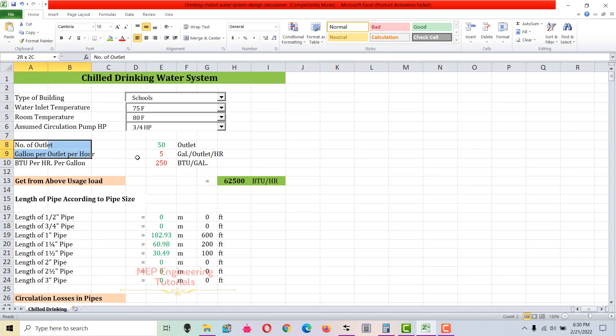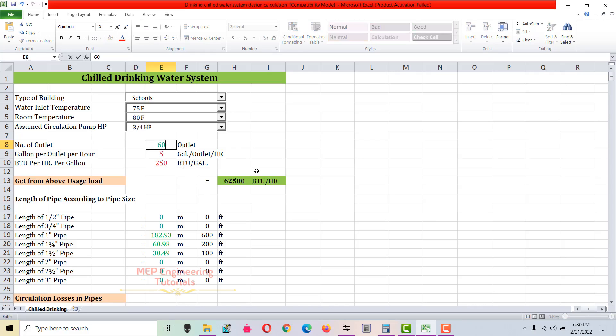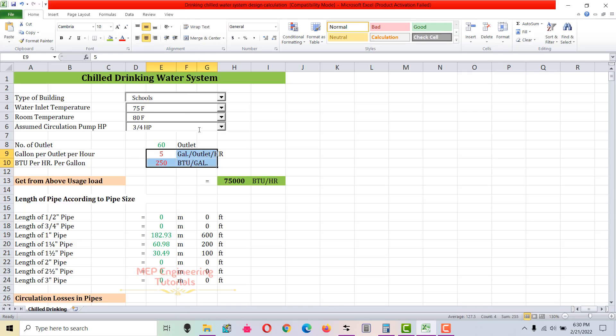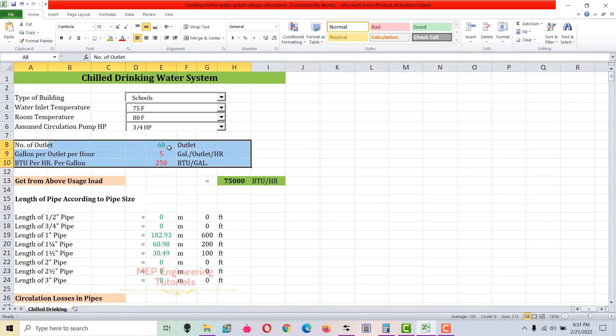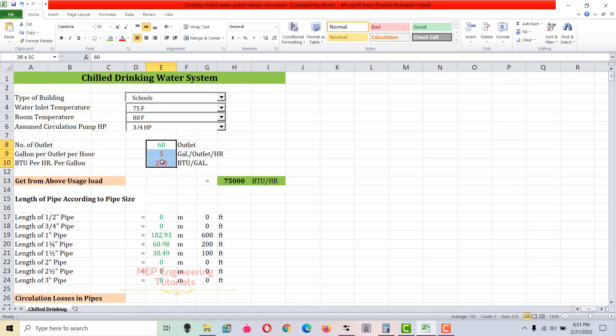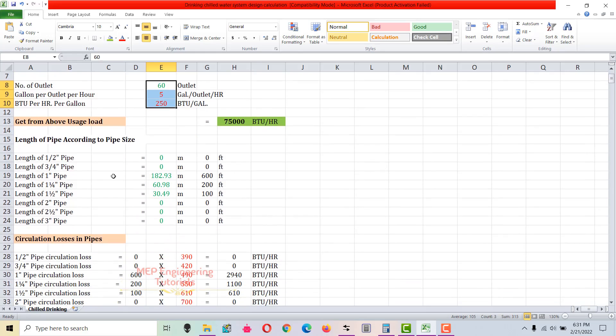Next, you have to count the number of outlets. Green color is the input from the user, so you have to go to the drawing, count the number of outlets, and enter it here. Let's say the number of outlets from the drawing is 60. Now we calculate the load due to usage — simply multiply these three values and you get 75,000 BTUs per hour.